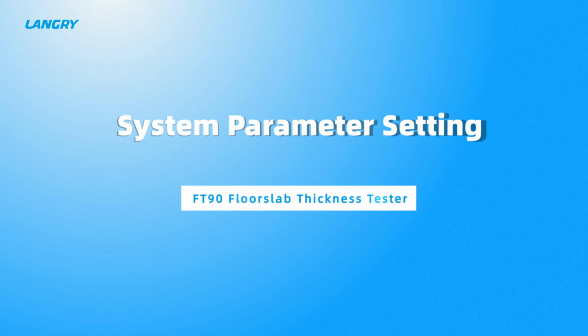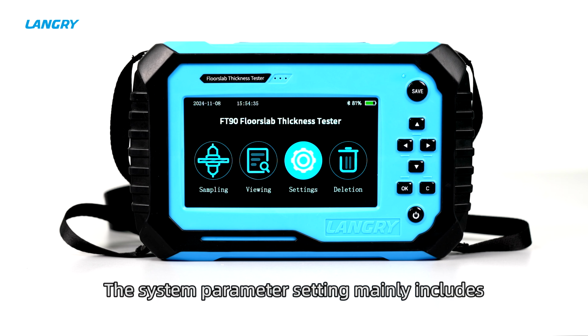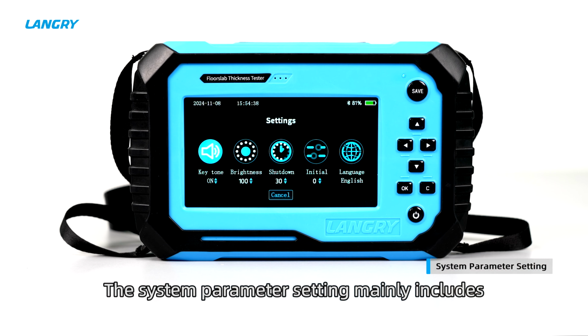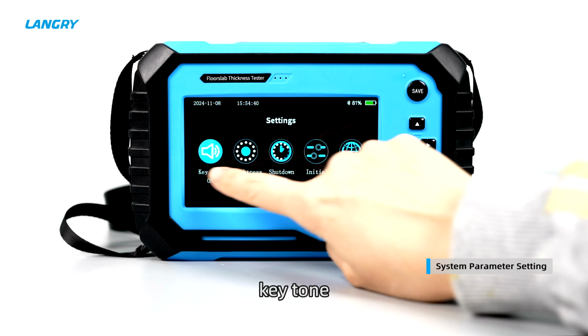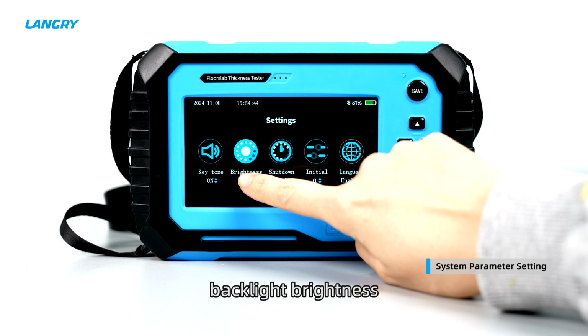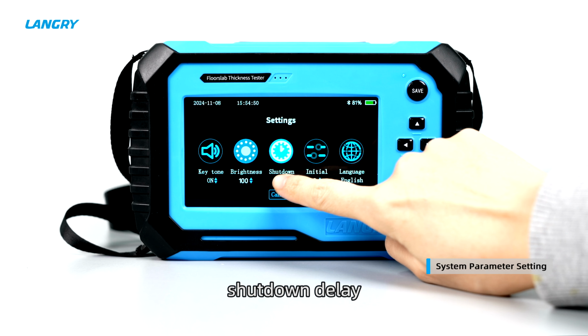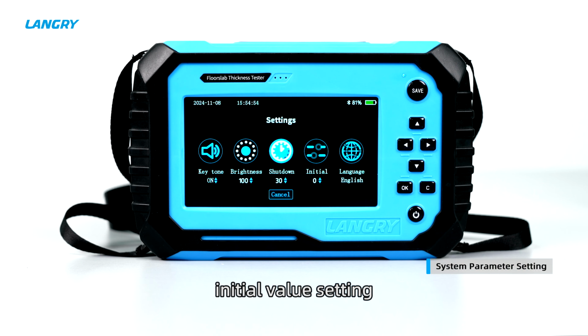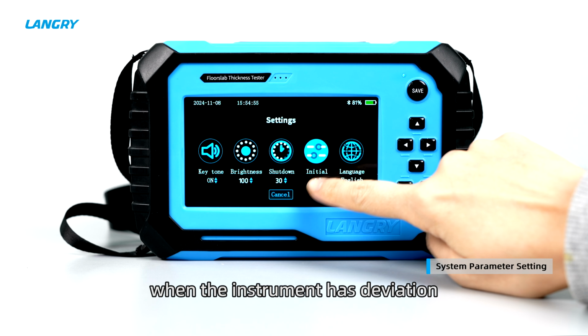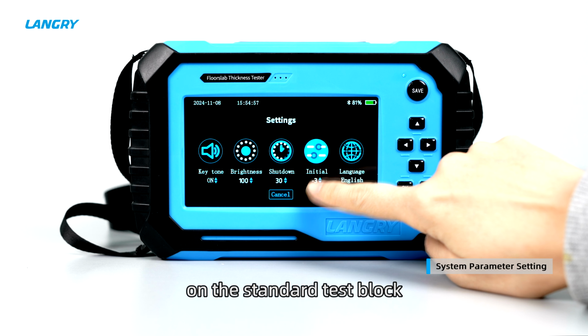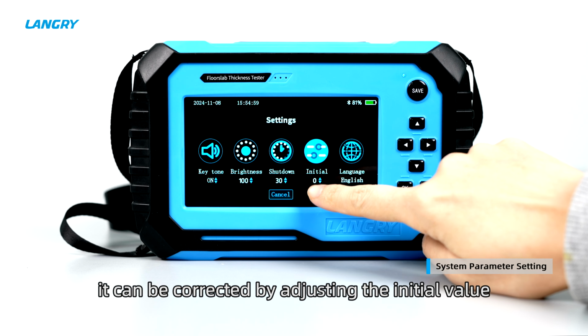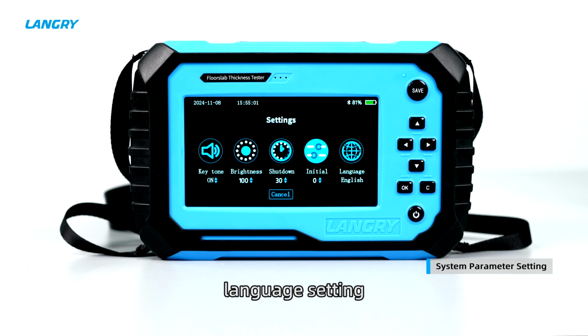7. System parameter setting. The system parameter setting mainly includes key tone, backlight brightness, shutdown delay, initial value setting. When the instrument has deviation on the standard test block, it can be corrected by adjusting the initial value. Language setting.